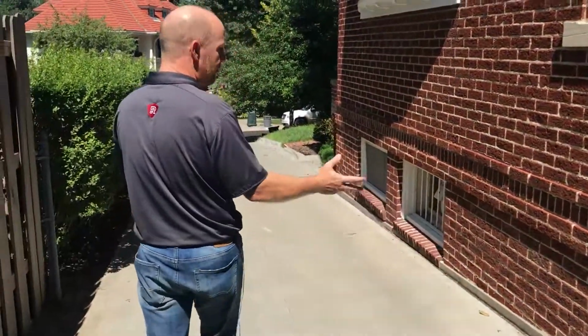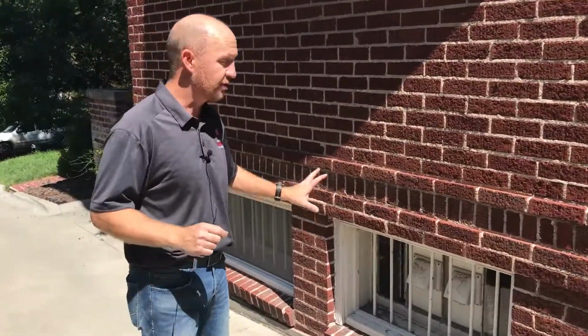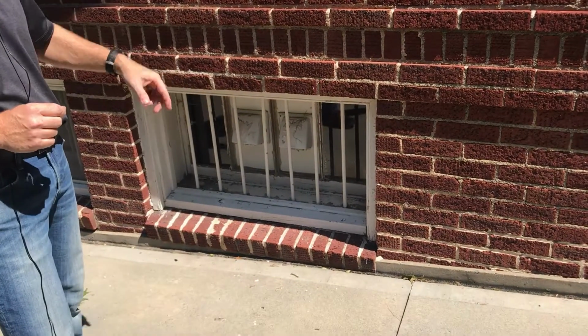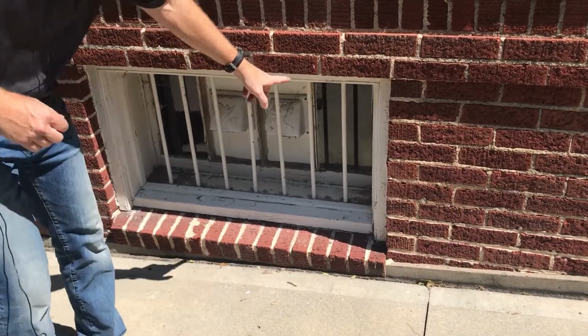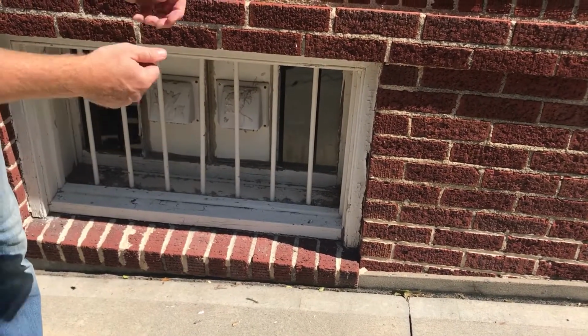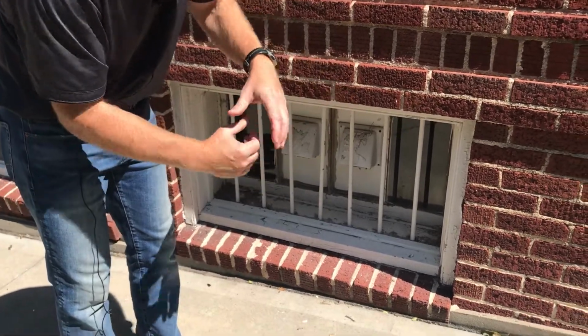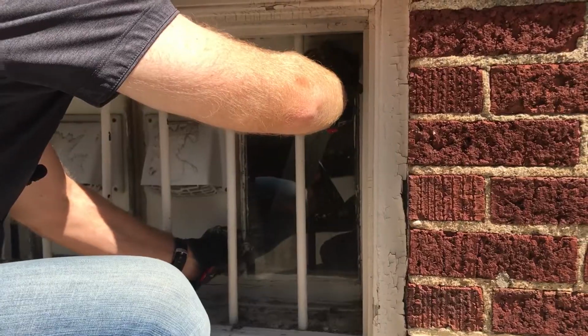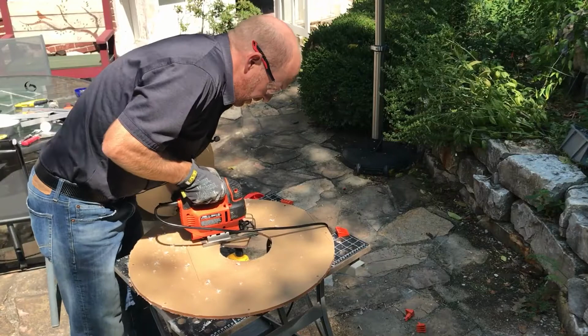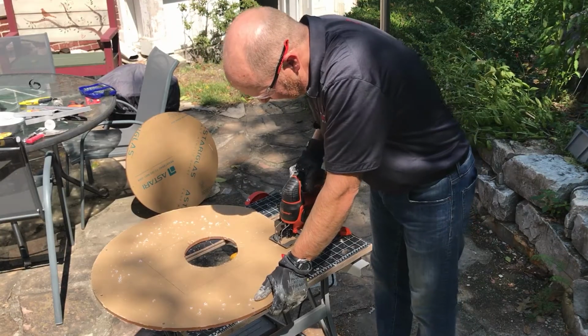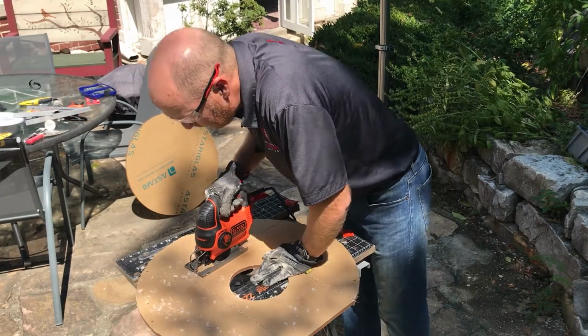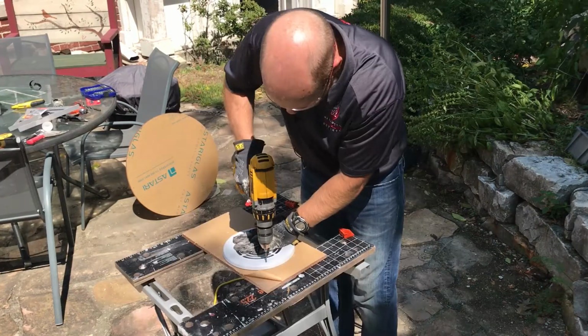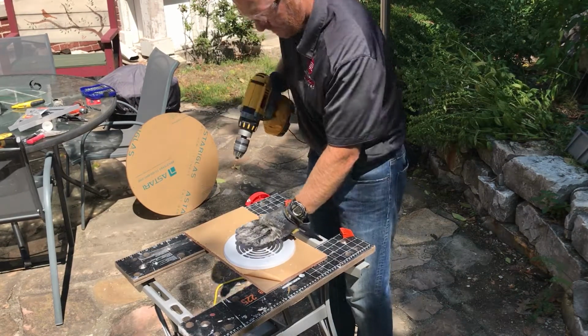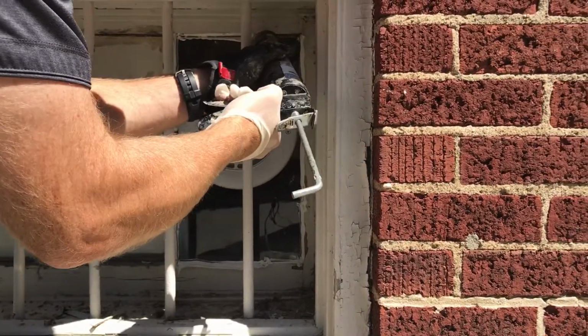And then down here, well over 10 feet away, we have the dryer vents exhausting outside. So we're actually going to use this spot for our exhaust of our ERV. We're going to go ahead and use a window right next to that, take the piece of glass out, put a piece of plexiglass in there, and then have our vent connection right to that. So that's our strategy for our intake and our exhaust of this ERV. We're removing the glass pane from this window and replacing it with a piece of plexiglass with a hole through it. The plexiglass that we're using is actually a lid that we would use potentially on a sump pit, that type of plexiglass. So you may already have that for some of your installs. And then we make a hole in it, connect our vent, and then caulk that into place.